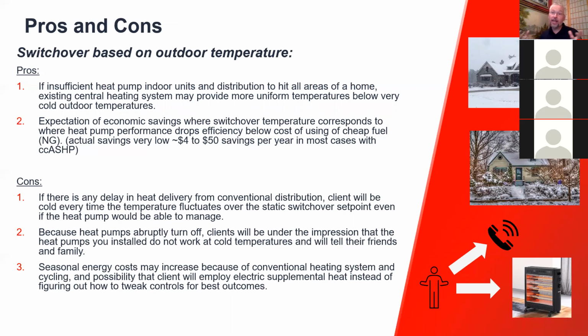Okay, and you could use a switchover temperature based on an economic balance point, as we already started to discuss, in order to provide some additional economic benefit. But even in the case of natural gas across this entire region, across the entire Northeast, the benefit of switching over and having perfect switching for natural gas, the maximum would be something around the ballpark of 5% seasonal savings. It's really not that great of a savings, even against the cheapest fuel. It's always cheaper to just run a heat pump against propane, and 99% of the time it's cheaper to run against oil. So I'd be careful about that.